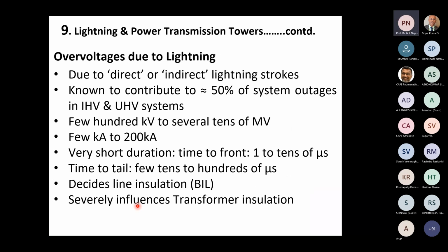Now some information. Due to direct or indirect lightning strokes, lightning voltages can occur on transmission lines. Lightning is known to contribute approximately 50% or more of the system outages in EHV and UHV systems. This is not HV, this is EHV. Please note that EHV and UHV systems: up to and including 220 kV is HV, 400 kV and higher, that means 400 kV, 800 kV, 1200 kV, are EHV and UHV systems. In all these systems, at least 50% of the outages are known to be due to lightning.